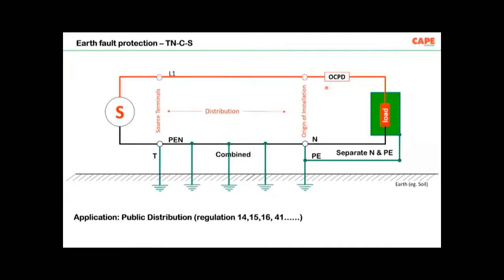Also, in the previous slide, I have shown the fault loop impedance, how earth fault protection is achieved in case of a TN-C-S system. TN-C-S is a system earthing which is generally used for public electricity distribution. In that particular case, imagine there is a fault here. The fault current is returning back to the source through the PEN conductor. The fault current is coming back to the fault through the live conductor. The impedance of this loop decides the amount of fault current, and the amount of fault current decides the disconnection time of the circuit or the protective device, such as an MCB.